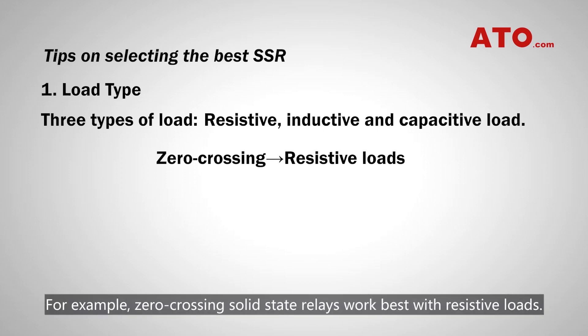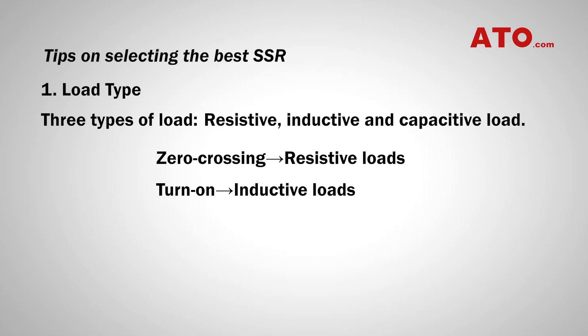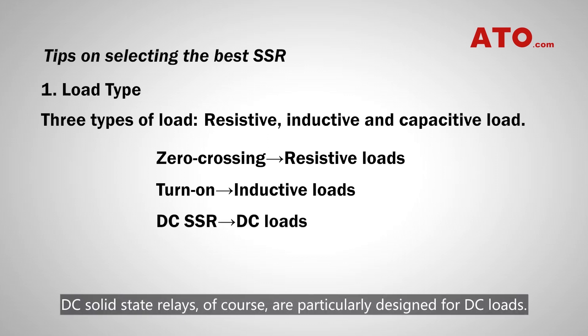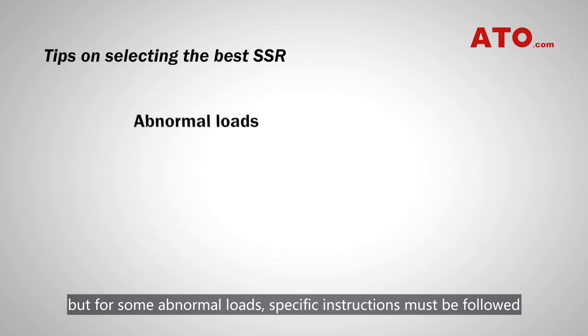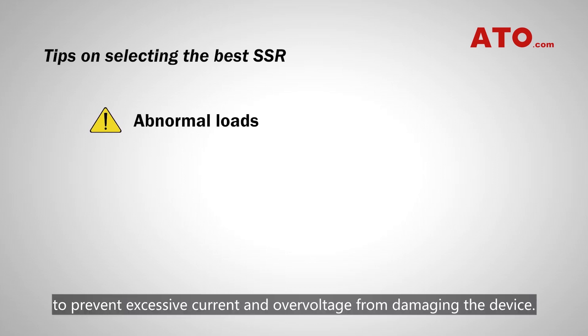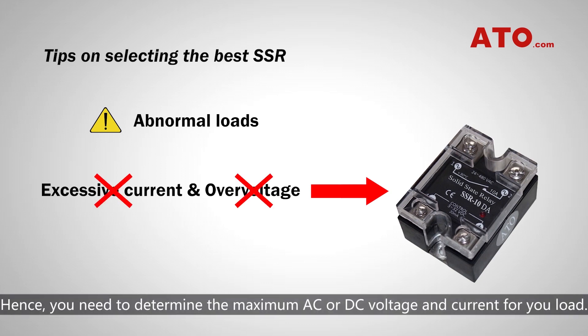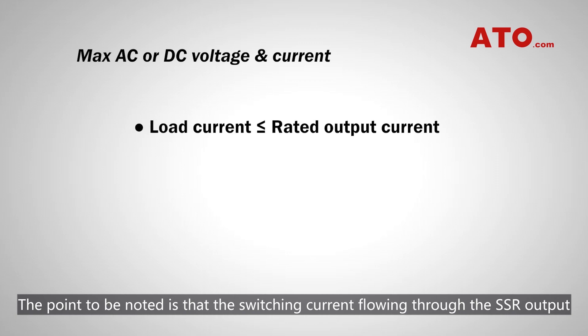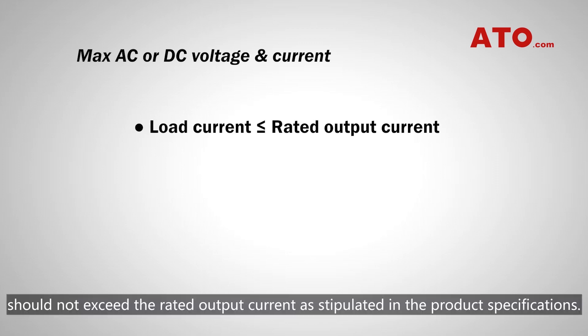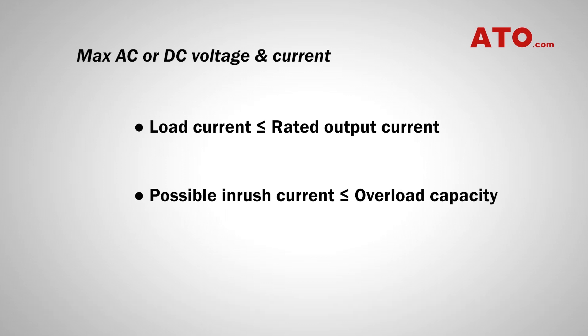For example, zero-crossing solid-state relays work best with resistive loads. Random turn-on solid-state relays are ideal for inductive loads. DC solid-state relays are particularly designed for DC loads. SSRs can switch normal loads on and off, but for some abnormal loads, specific instructions must be followed to prevent excessive current and overvoltage from damaging the device. Hence, you need to determine the maximum AC or DC voltage and current for your load. The switching current flowing through the SSR output should not exceed the rated output current as stipulated in the product specifications, and the possible in-rush current must not exceed the overload capacity of the relay.